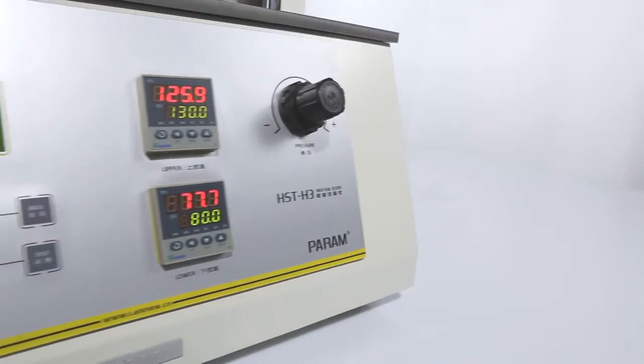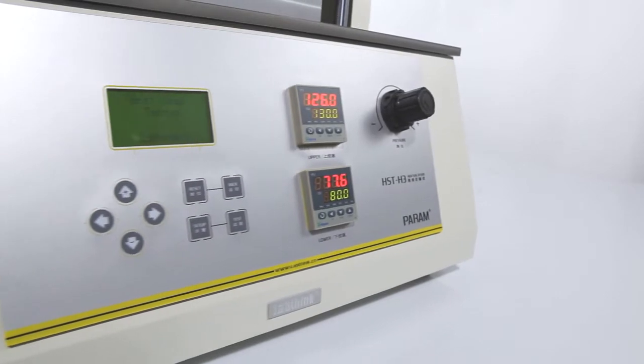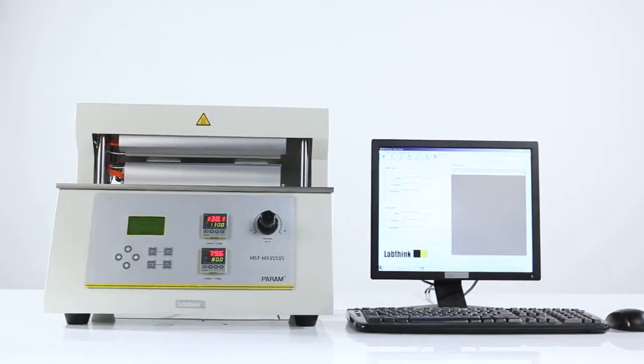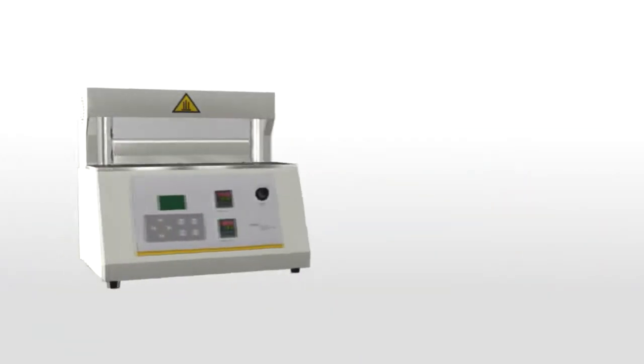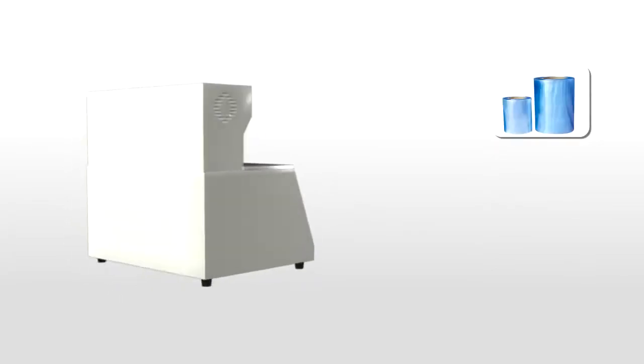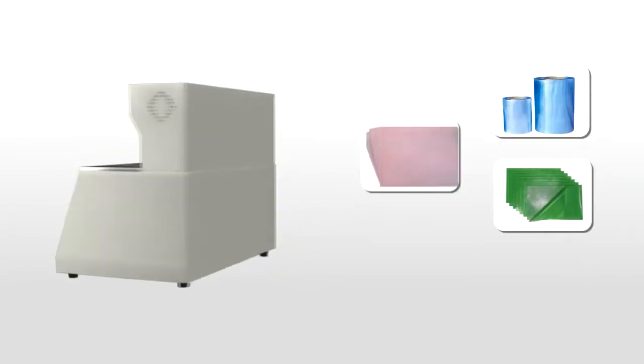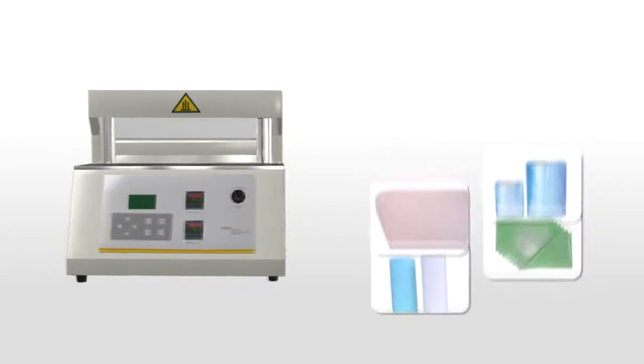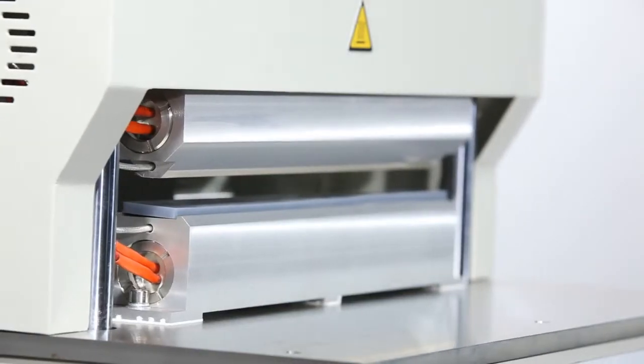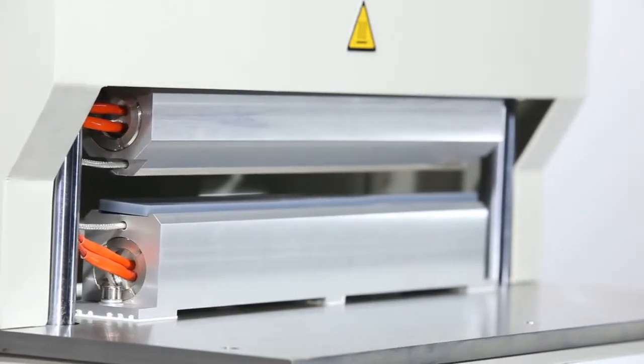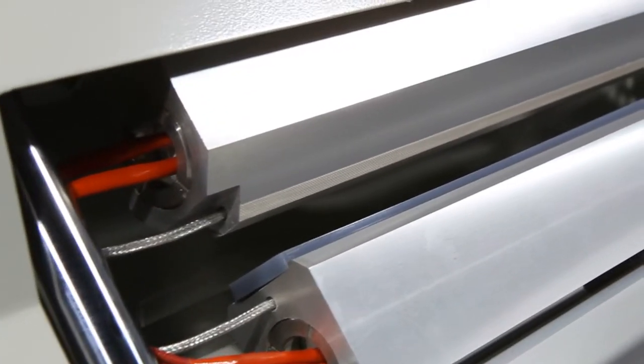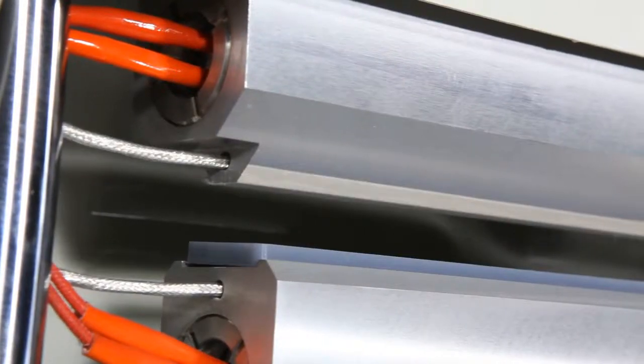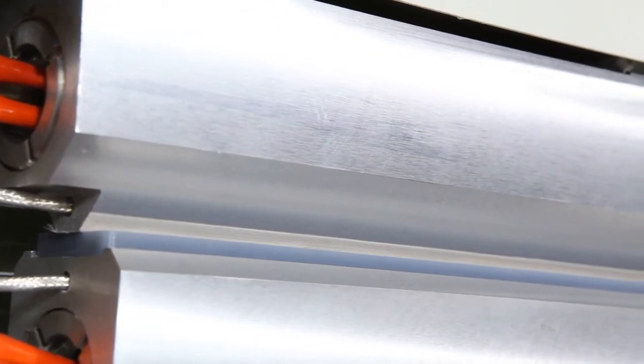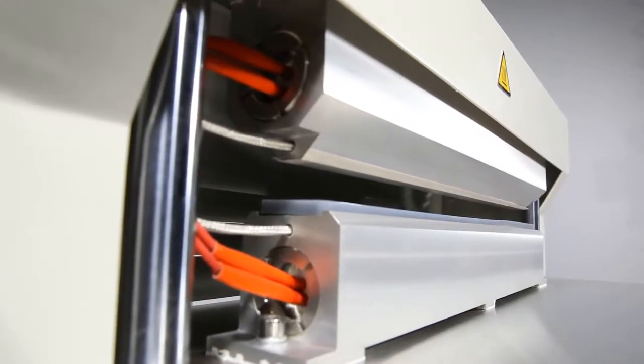HST-H3 is Labthink's best-selling heat seal tester, which is used to determine the heat sealability of flexible webs such as basic films, laminated films, coated paper, and other heat sealing laminated films. Independent temperature control of the upper and lower jaws of the heat sealer and the aluminum encapsulated heating tubes ensure an even temperature along the sealing jaws.